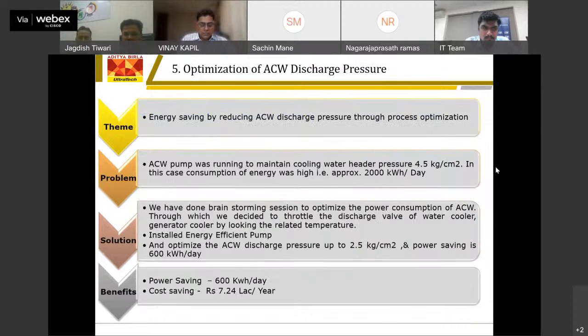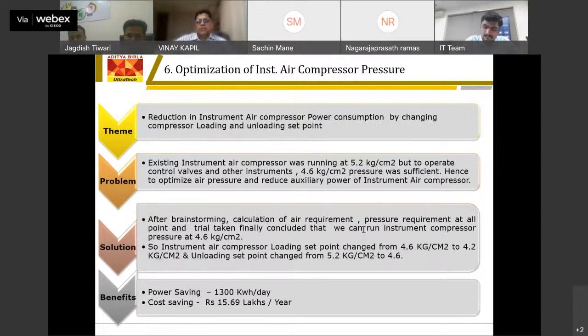Fifth one is the optimization of ACW discharge pressure, which is also a process optimization. Through brainstorming we identified excess pressure of water, which we can reduce and throttle while maintaining our related parameters and temperatures. Earlier we were running at 4.5 kg discharge pressure, and now we have optimized it to 2.5 kg per centimeter square, which can give a saving of 600 kWh, and the monitored saving is 7.24 lakhs per annum, sir.